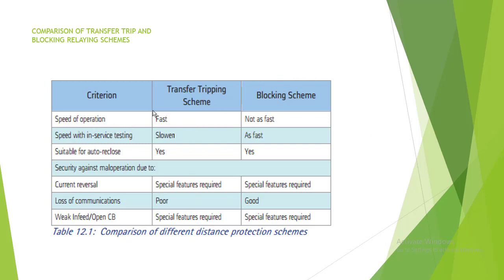Speed of operation: in the transfer tripping scheme it is fast, whereas in the blocking scheme it is not as fast, because the relay has to wait for a predefined time of 100 to 200 milliseconds. If the blocking signal is not coming, it has to wait for the complete time before it can issue a trip.